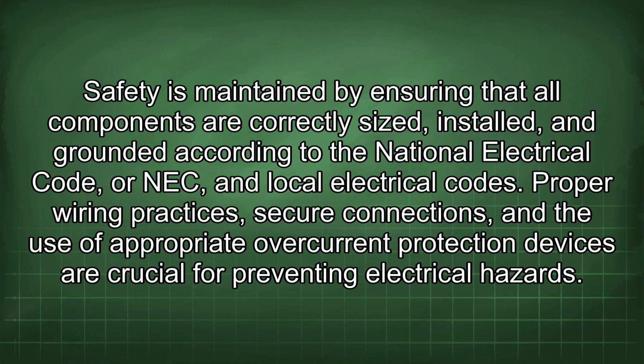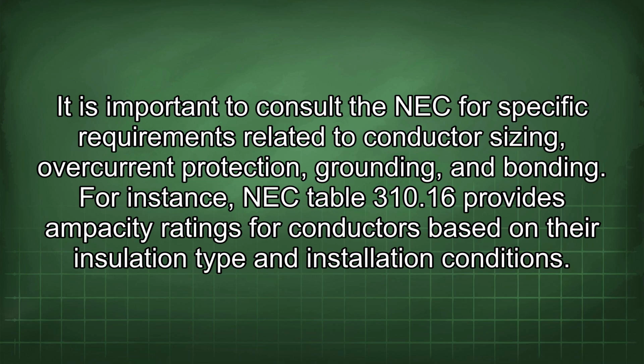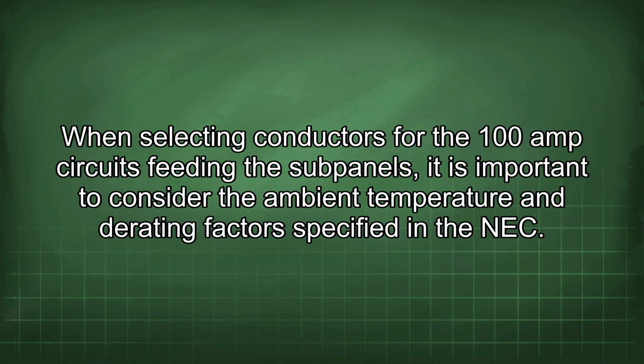Proper wiring practices, secure connections, and the use of appropriate overcurrent protection devices are crucial for preventing electrical hazards. It is important to consult the NEC for specific requirements related to conductor sizing, overcurrent protection, grounding, and bonding. For instance, NEC Table 310.16 provides ampacity ratings for conductors based on their insulation type and installation conditions. When selecting conductors for the 100 amp circuits feeding the subpanels, it is important to consider the ambient temperature and derating factors specified in the NEC.